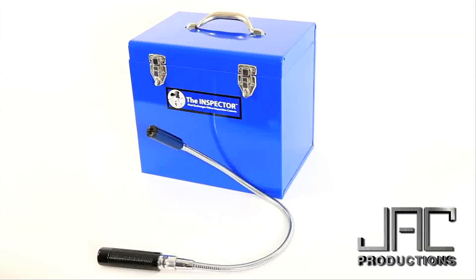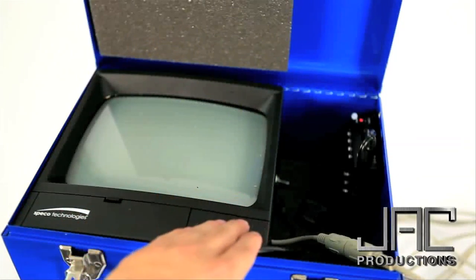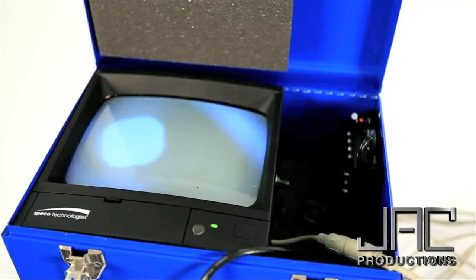The inspector camera is just fantastic. The quality, the resolution — you can really pull up defects in the heat exchanger and blow it up to the size that even a 90-year-old lady can look in there and see that it's obviously a defect.